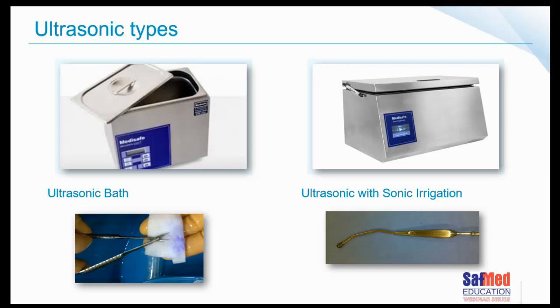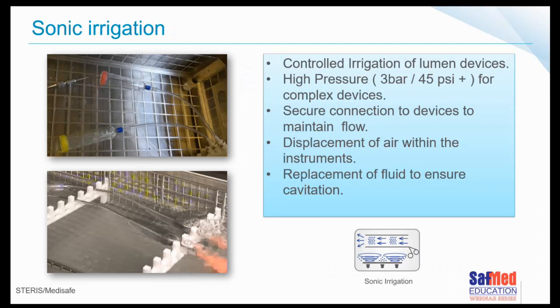So we've already alluded to the fact that there are generally two types of ultrasonic cleaners that we are going to use in the healthcare setting. The one being a bath, and of course those baths are available in different sizes or different volumes, depending on your needs. And again, ideal for delicate instruments, ideal for eye instrumentation. And then ultrasonics with sonic irrigation. Sonic irrigation, absolutely critical for obviously certain lumen devices. When you have an ultrasonic cleaner with sonic irrigation, it means that the external surfaces as well as the internal surfaces are being exposed to ultrasonic energy.